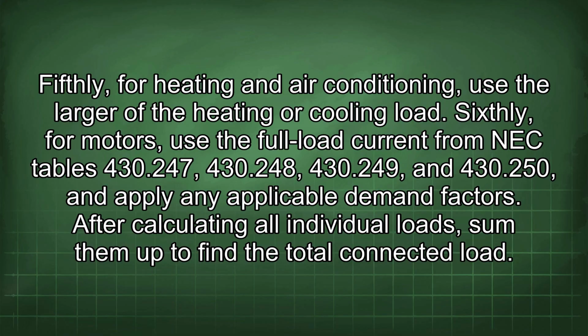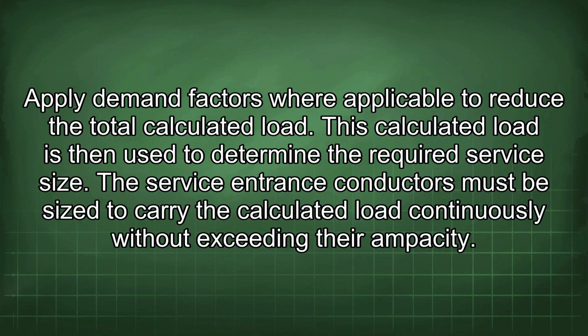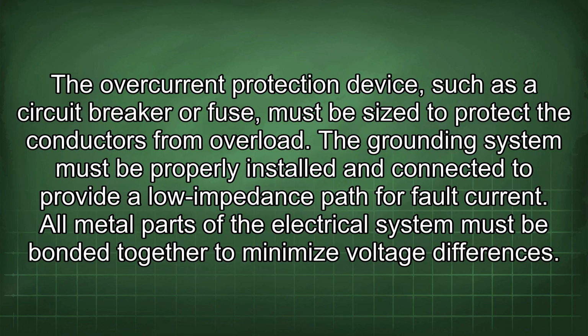After calculating all individual loads, sum them up to find the total connected load. Apply demand factors where applicable to reduce the total calculated load. This calculated load is then used to determine the required service size. The service entrance conductors must be sized to carry the calculated load continuously without exceeding their ampacity. The overcurrent protection device, such as a circuit breaker or fuse, must be sized to protect the conductors from overload.